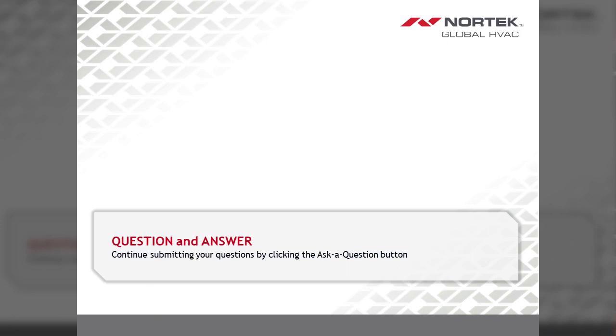Okay, another question that we have is in regards to checking flame signals. I didn't talk about that in the presentation here, but all that you really have to do in regards to checking flame signal is, one, it's going to be a micro DC amp, so your meter has to have that unit of measurement in order to check flame signal. So that's one thing we need to make sure on.